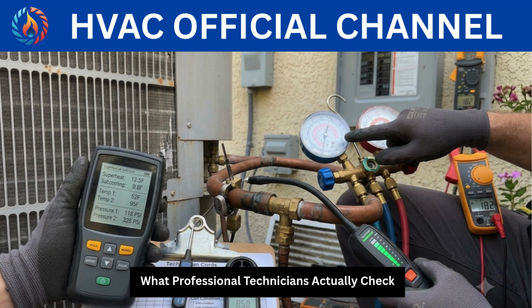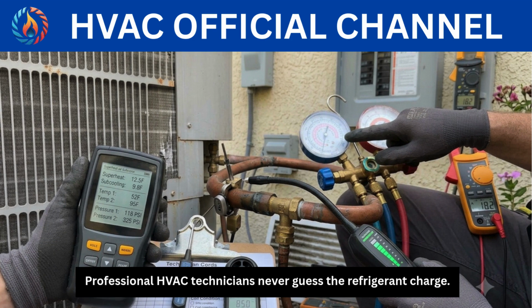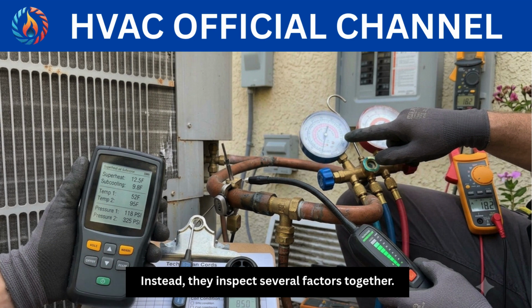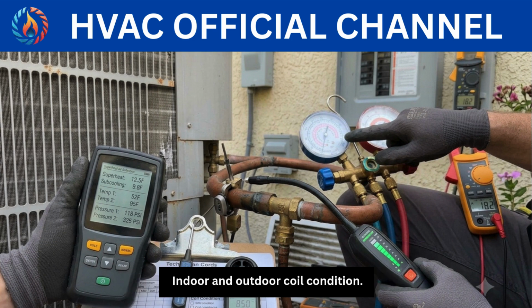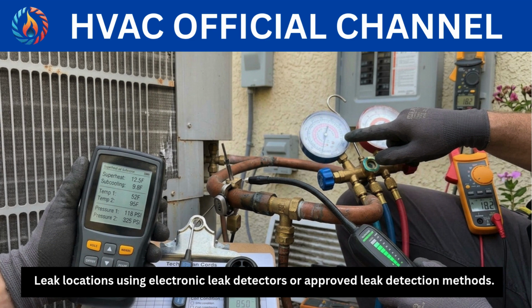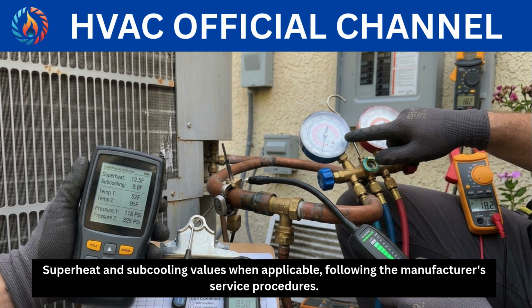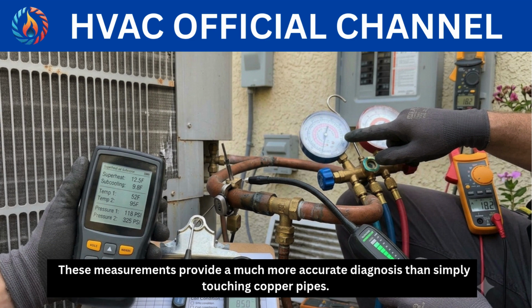What professional technicians actually check? Professional HVAC technicians never guess the refrigerant charge. Instead, they inspect several factors together. They check operating pressures using a manifold gauge set, airflow across the evaporator and condenser, supply and return air temperatures, electrical current drawn by the compressor, indoor and outdoor coil condition, leak locations using electronic leak detectors or approved leak detection methods, superheat and subcooling values when applicable, following the manufacturer's service procedures. These measurements provide a much more accurate diagnosis than simply touching copper pipes.